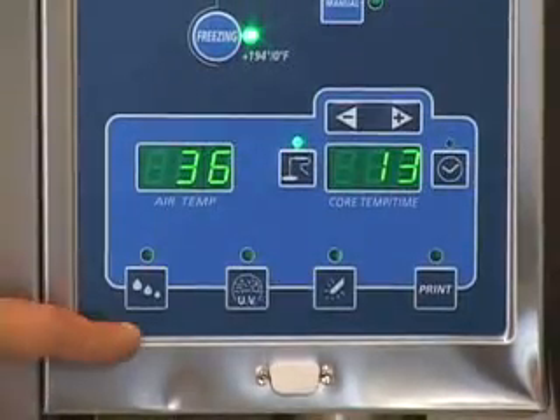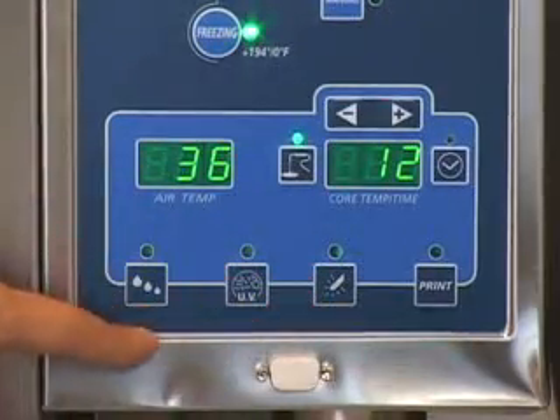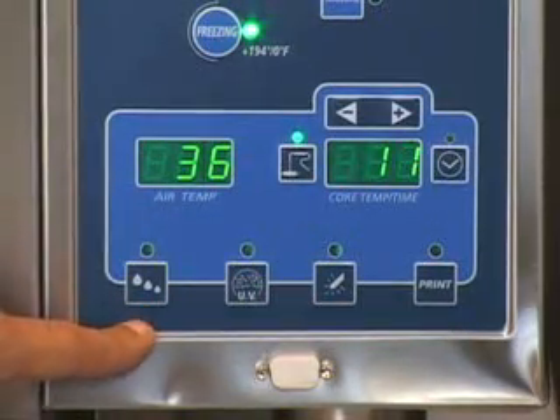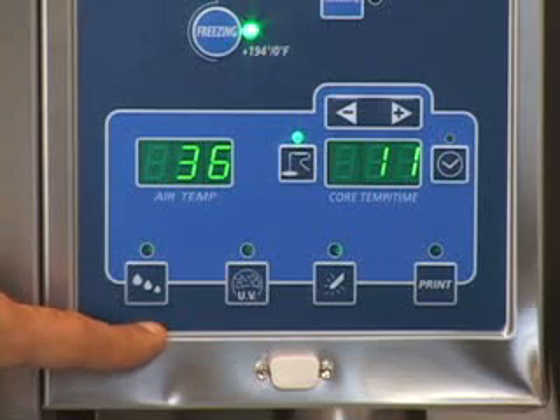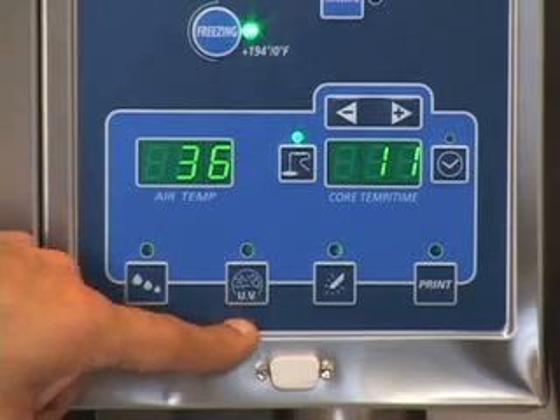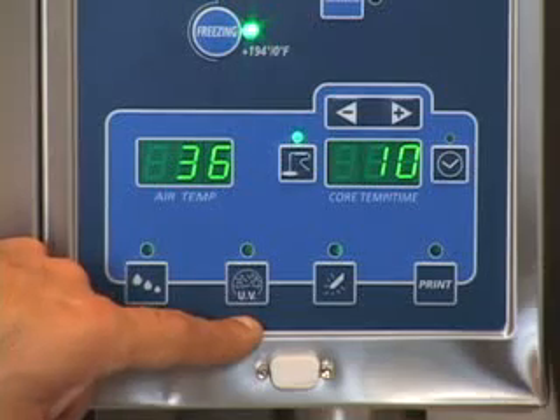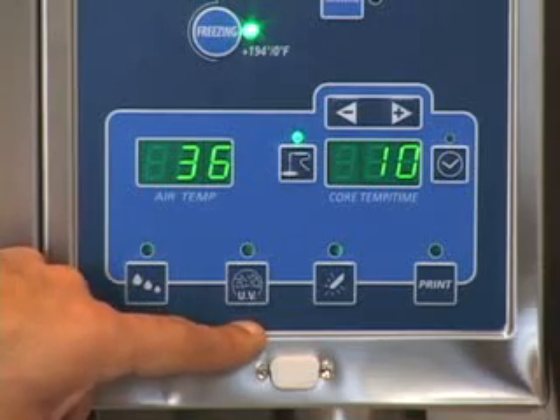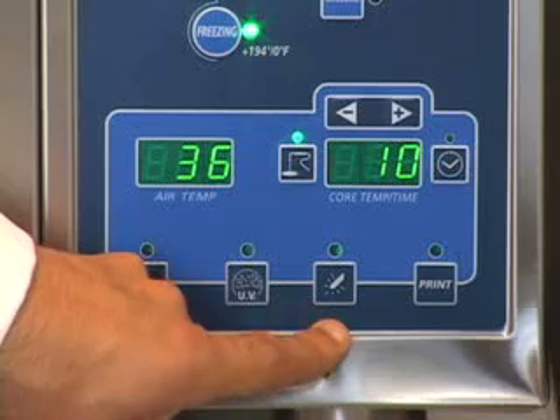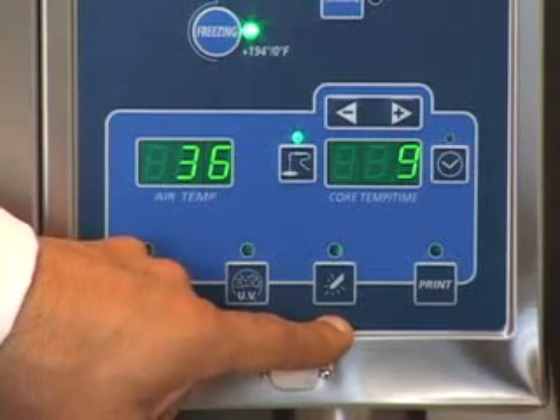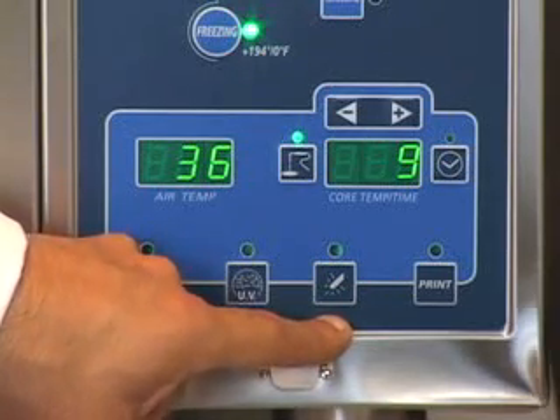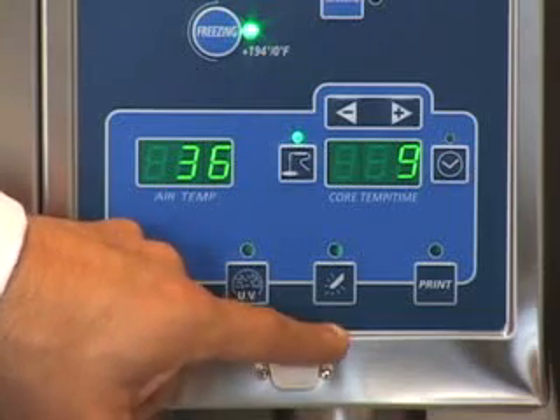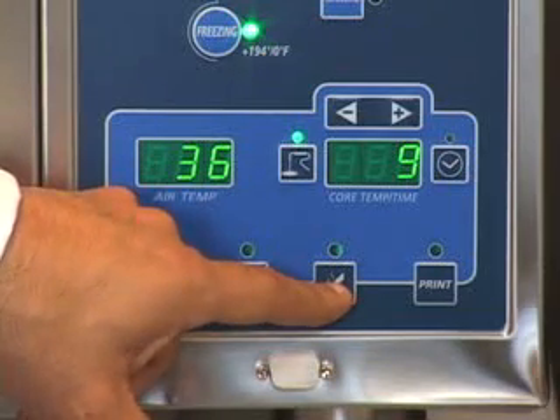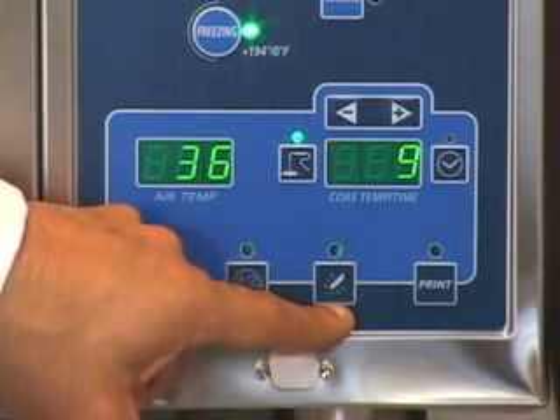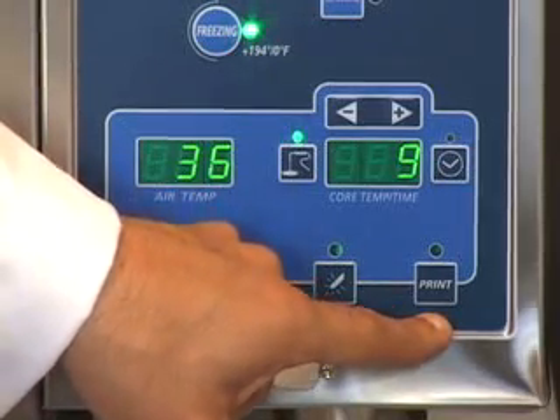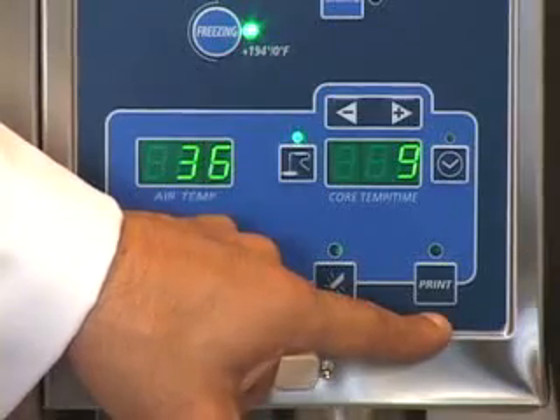Now I'm going to explain to you the 4 buttons on the lower part of the controller. The first button with the 3 drops is the defrost button. It's for controlling the manual defrost of the unit. This button here, the UV sterilization button, is if you have the optional UV sterilization system installed. The third button is for probe heat. When you've shock frozen a product and the probe is stuck in the product, you can use the probe heater button, which will heat the probe for 5 seconds so it's easily removed. And then you have the print button, which is for an optional handheld printer.